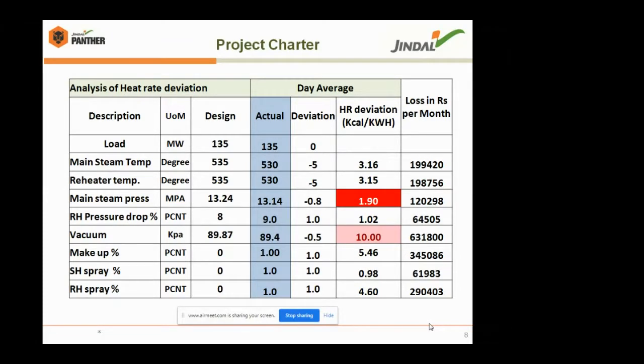In case of vacuum, the design vacuum is 89.87 kilopascal. If we are deviating by 0.5 kilopascal, the loss of turbine heat rate is 10 kilocalorie per kilowatt hour, which is equivalent to 6 lakhs. Similarly, in makeup percentage, ideally it is 0, but if it deviates by 1%, the loss of heat rate is 5.46 kilocalorie per kilowatt hour, equivalent to 3.5 lakhs per month.